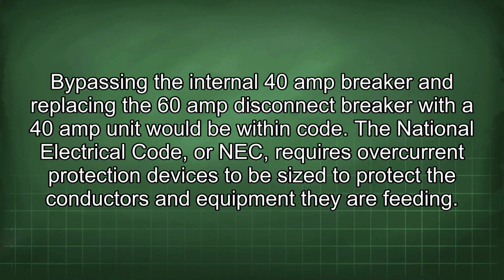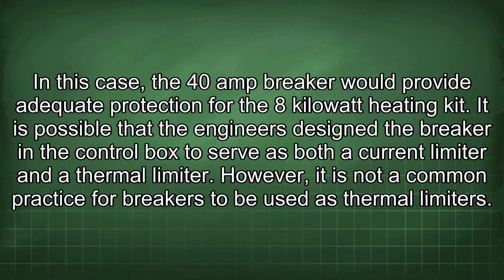Bypassing the internal 40 amp breaker and replacing the 60 amp disconnect breaker with a 40 amp unit would be within code. The National Electrical Code, or NEC, requires overcurrent protection devices to be sized to protect the conductors and equipment they are feeding.